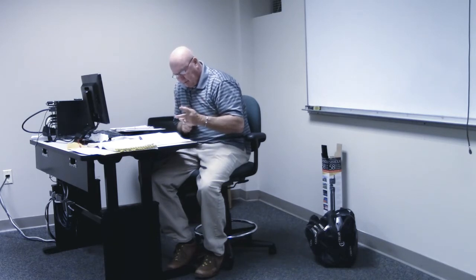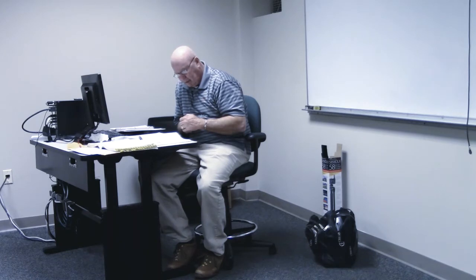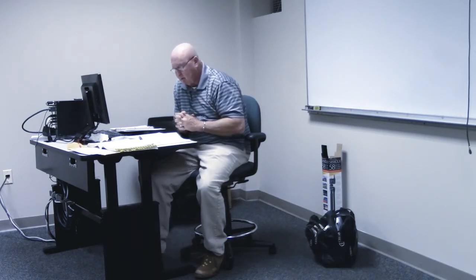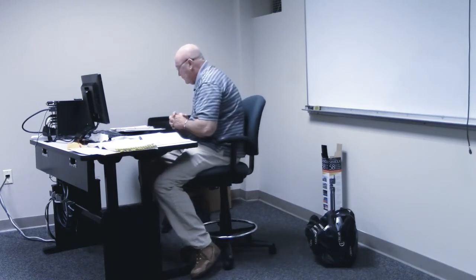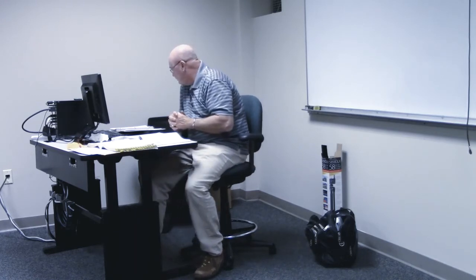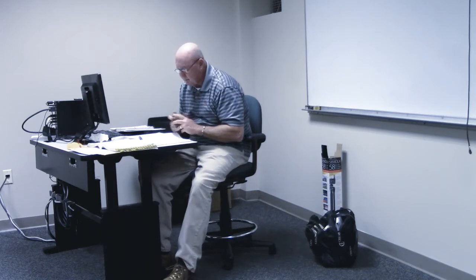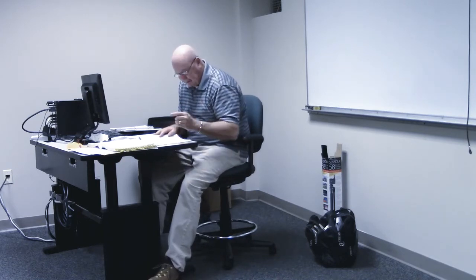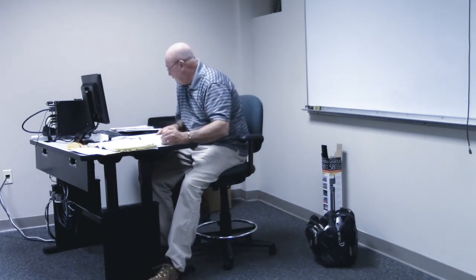Isolated conductor number 1: orange, with at least one distinctive color stripe other than white, green, or gray along the entire length of the conductor. So it's got to be orange. I'd probably know that. That's isolated conductor number 1 — not like number 1 is the size, but that one's got to be orange.